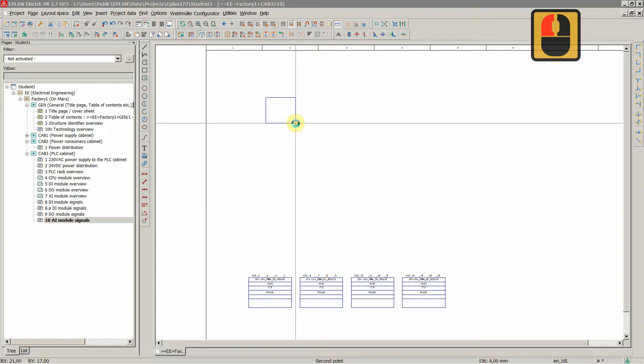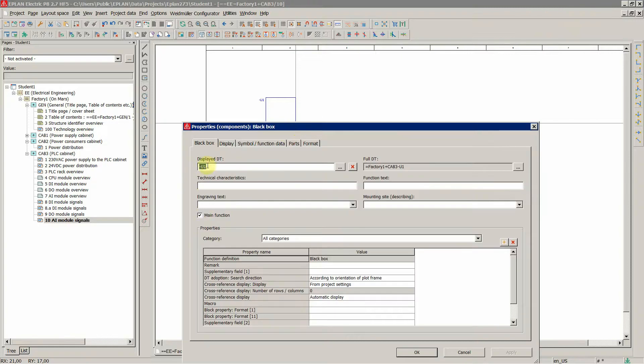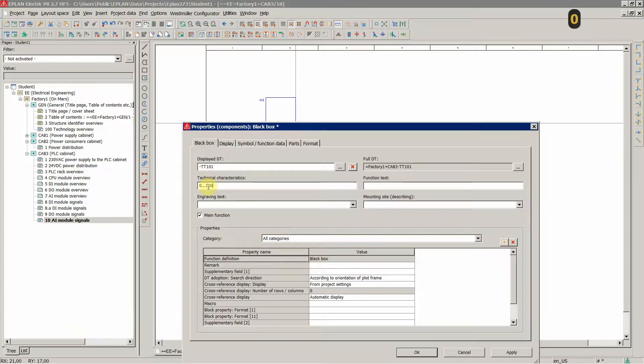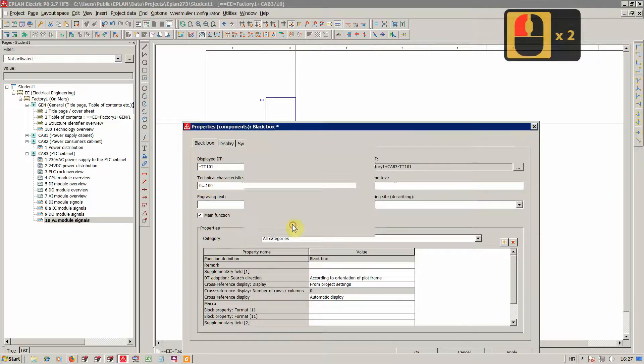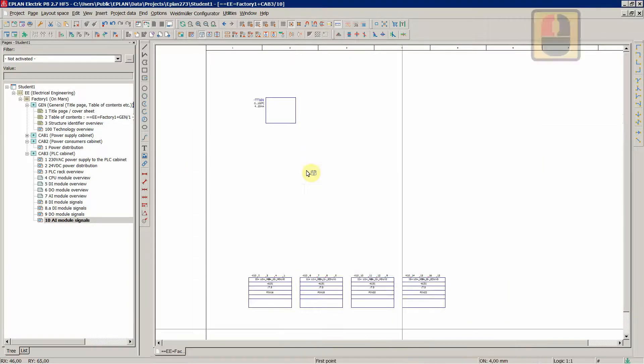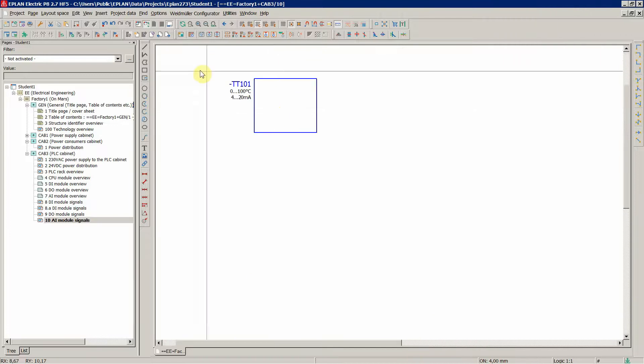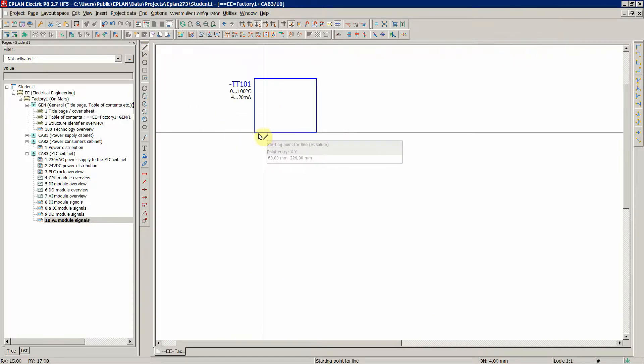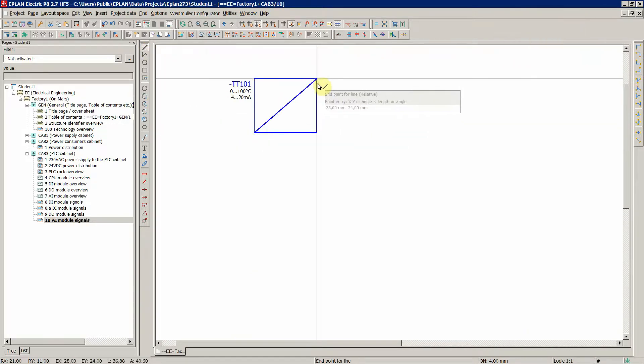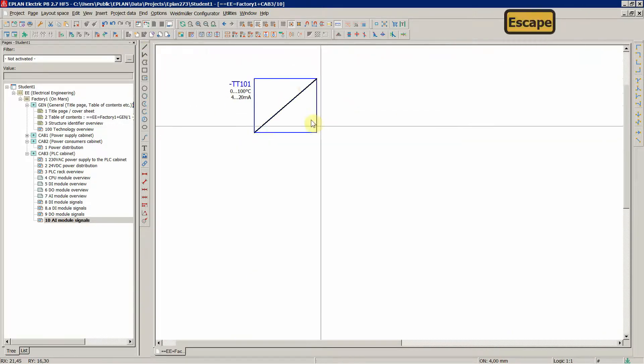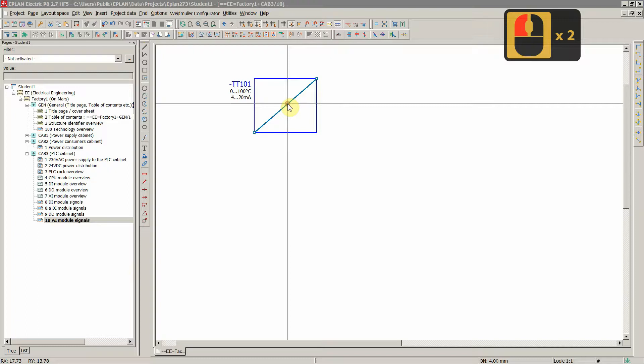So this is an instrument, we are measuring a temperature. We have a PT100 element as an example. And this instrument has additionally a transmitter in head, so it converts the resistance of the PT100 element to standard current signal of 4 to 20 mA.